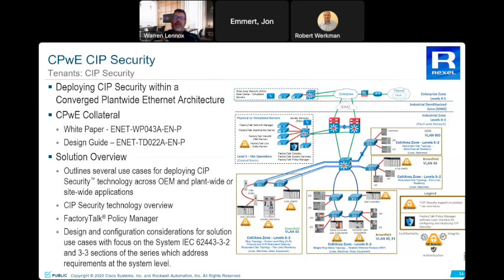If that's the case, we have to find a way to encrypt the communications. And that's what we do with CIP security. So first we'll do authenticity. There'll be a certificate exchange between the two devices. We'll do integrity, and then we can do confidentiality on the data itself. So encrypting the communications and then unencrypting it at the other end. Completely eliminating the possibility of a man-in-the-middle attack, someone being able to penetrate the system, bypassing all your software security realms, even bypassing your segmented switch areas. If they had to plug into the network, they would not be able to hear or listen to anything.